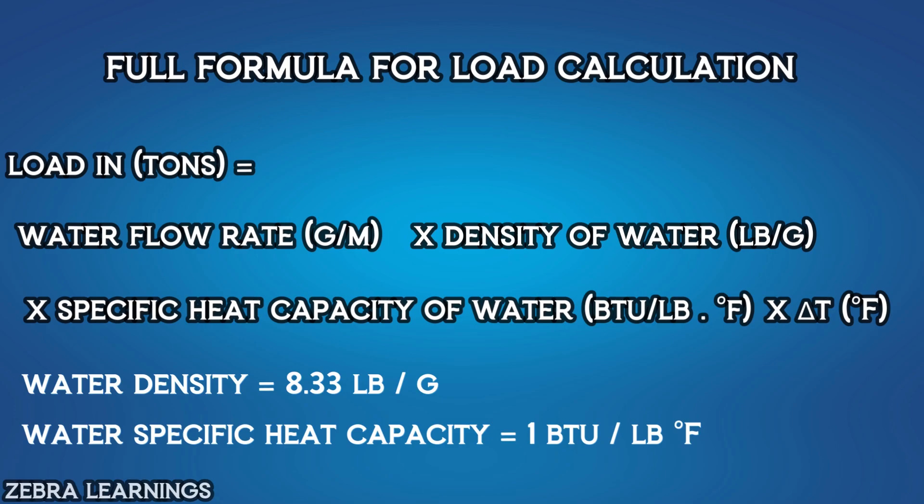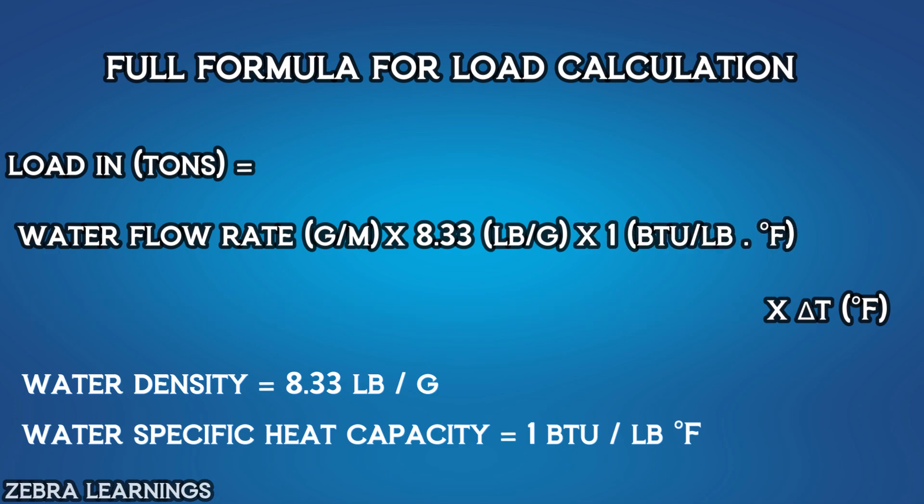Now let's use water flow rate in gallon per minute, multiply 8.33 pounds per gallon, multiply 1 BTU per pound degree Fahrenheit, multiply delta T in degree Fahrenheit.